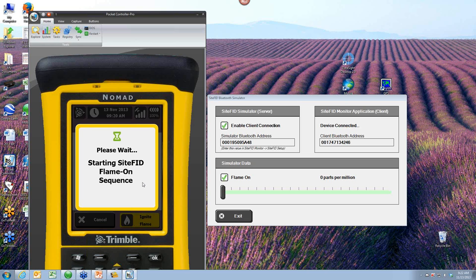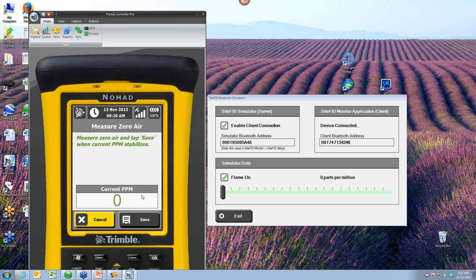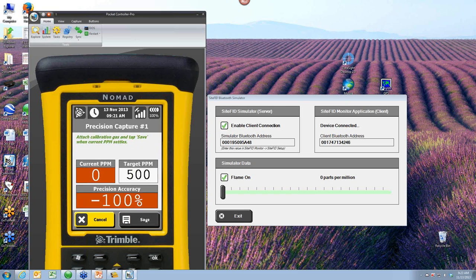And this makes it very easy for your field crews too, because if they skip a step, if they forget something, the software is smart enough to say, hey, you forgot to do something. So now the flame is on, I'm ready to go, I can do my calibrations. So it's looking for a 0 calibration first. This little scale over here, as you see as I raise and lower that, see how my ppms are going up. So the first thing we're looking for is a 0, and I'm just going to set it at 0 and hit save.